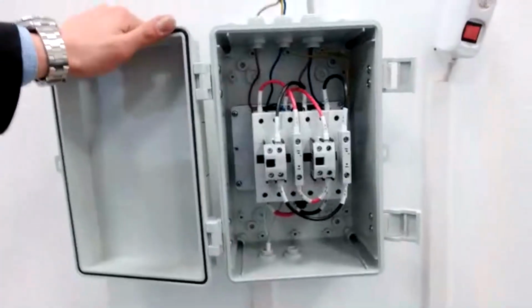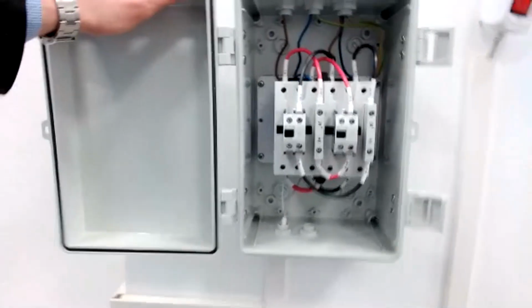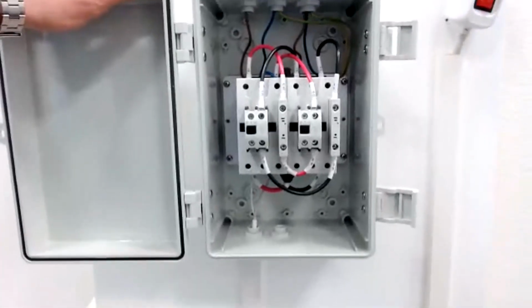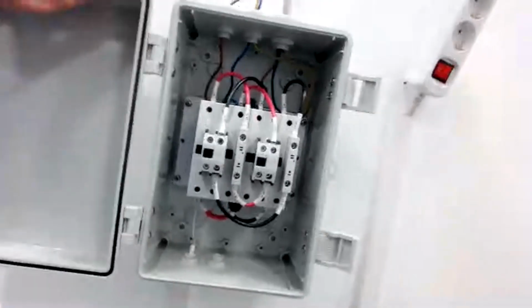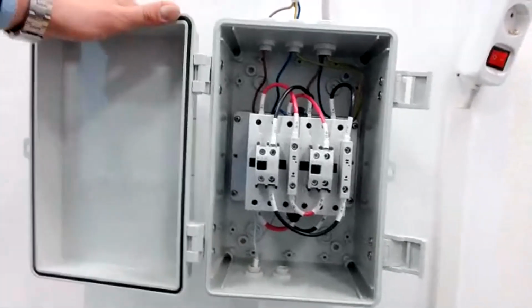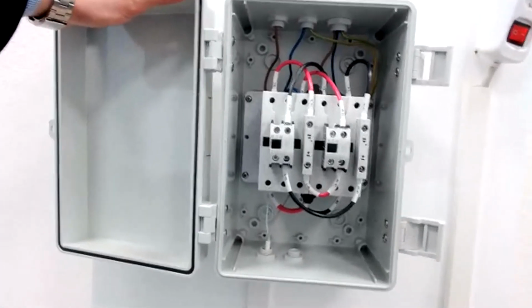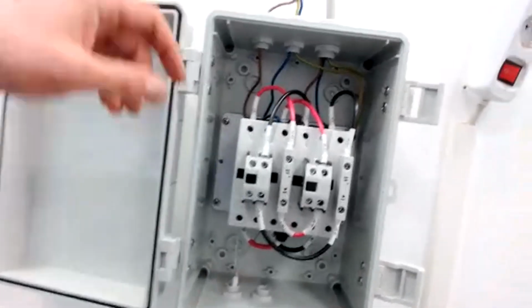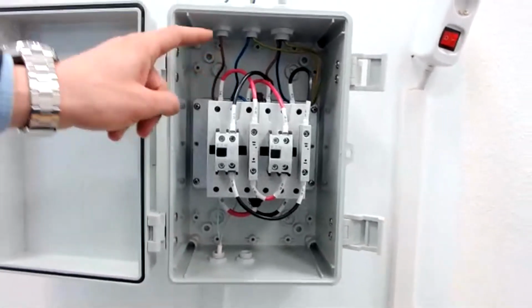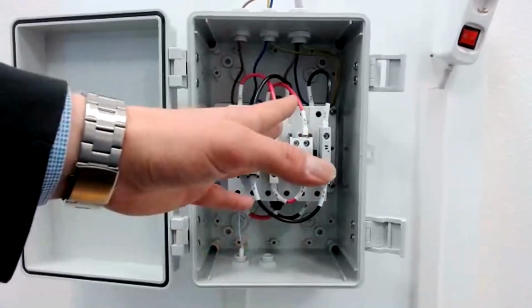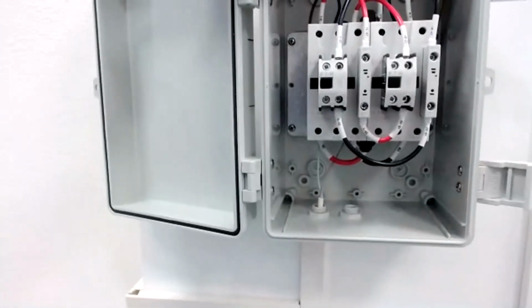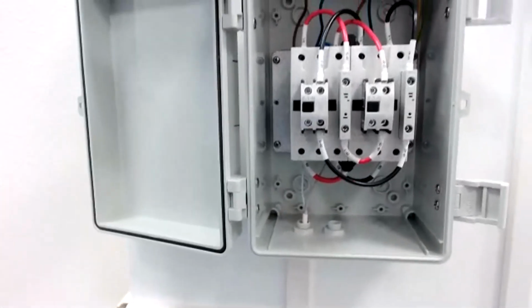You have this EPS box, which is connected to the grid and to the inverter. What it does is check all the time if the grid is available. As soon as it recognizes there is no grid available, it switches off to the off-grid mode, so there's no grid connection anymore. This happens really fast, and I'll show you how fast when I demonstrate it. As you can see, this one is already pre-connected when you get it.